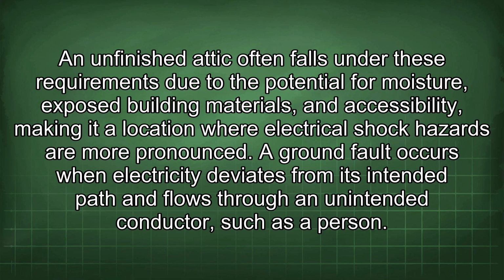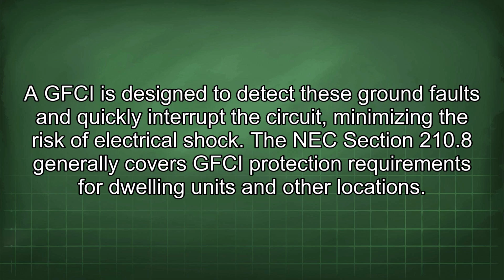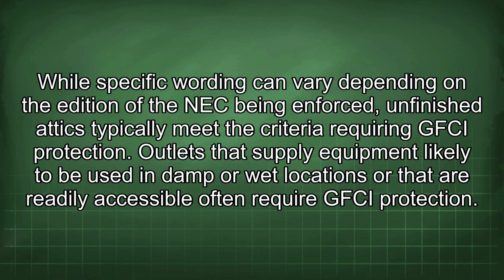A ground fault occurs when electricity deviates from its intended path and flows through an unintended conductor, such as a person. A GFCI is designed to detect these ground faults and quickly interrupt the circuit, minimizing the risk of electrical shock. The NEC Section 210.8 generally covers GFCI protection requirements for dwelling units and other locations. While specific wording can vary depending on the edition of the NEC being enforced, unfinished attics typically meet the criteria requiring GFCI protection. Outlets that supply equipment likely to be used in damp or wet locations or that are readily accessible often require GFCI protection.